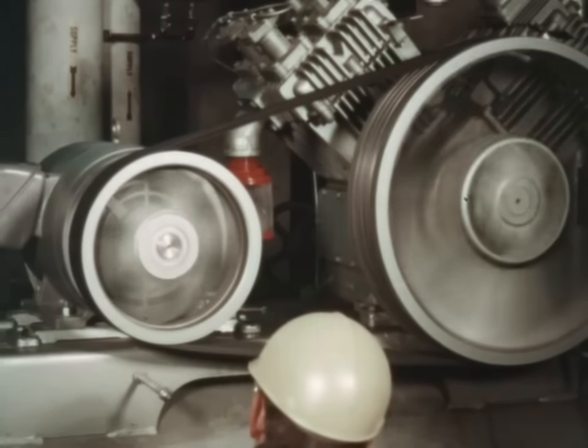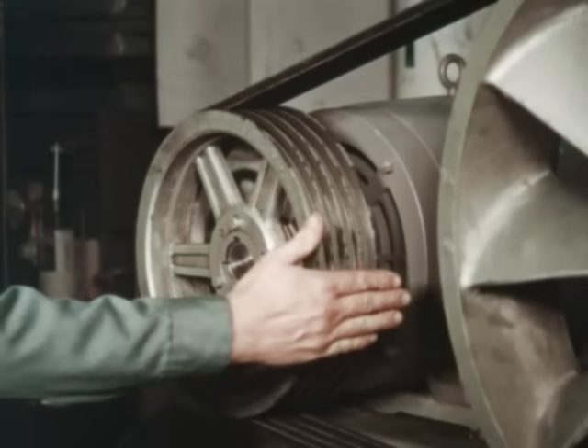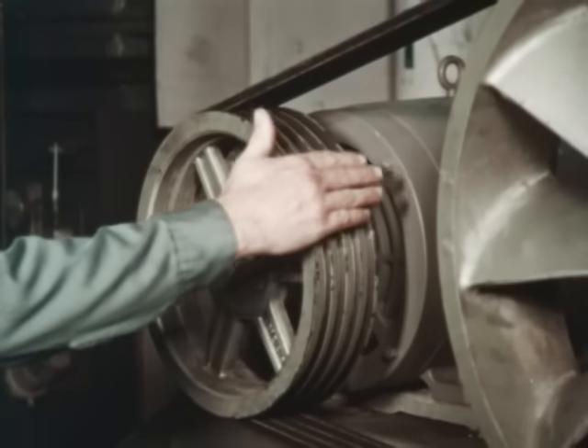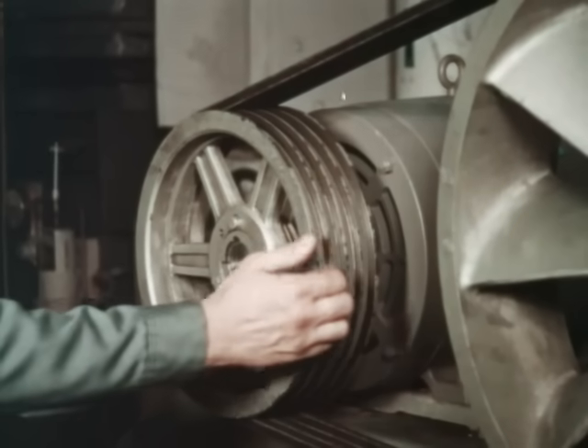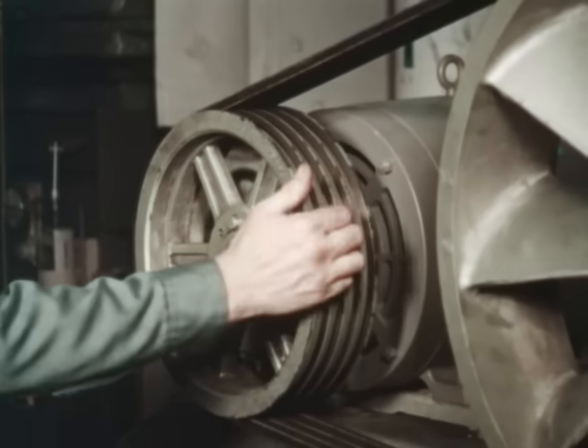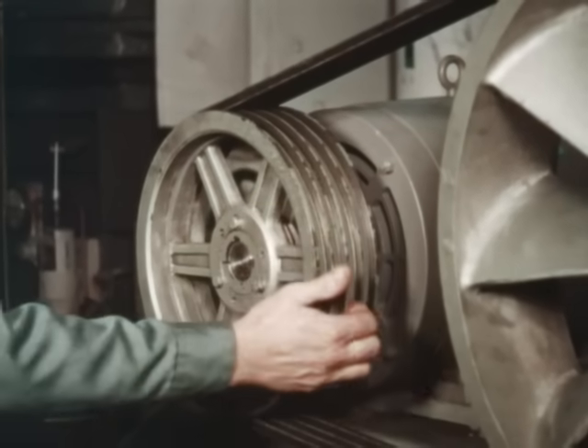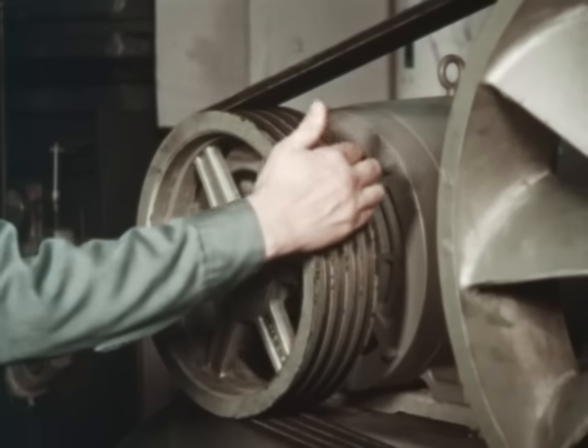Tighten the belts until the squeal is no longer heard. Using the hands, feel the sheave grooves — they should not be running hot. If the mechanic can place his hand in the groove for any period of time, then they are running cool enough. Hot sheave grooves are usually caused by belts whose wedging action is lost, resulting in belt slippage.